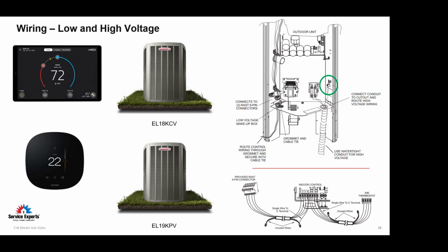When pairing the communicating equipment with the S40 or any of the communicating thermostats, follow the wiring instructions as per the installation manual, utilizing the RAST connector that you can see right there highlighted. Any unused low voltage connectors can create an antenna. So as you can see, the unused wires are kind of together there in the Marrettes. And then that low voltage, there's one conductor that goes back to common, low voltage common. So that, God forbid, if there's ever any sort of electrical noise on any of those unused wires, it won't disrupt the low voltage DC signal being sent back and forth down the I+ and I- control wires.